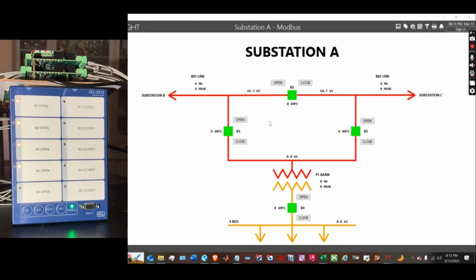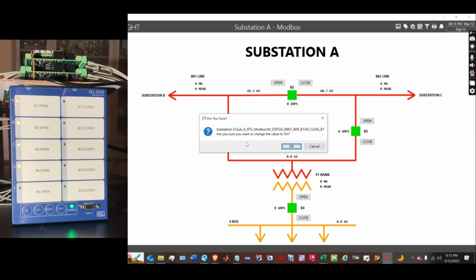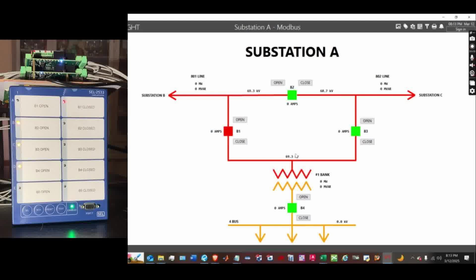are 0. After closing breaker B1 from the SCADA, we get our little pop-up window here asking us to confirm, do we want to close breaker B1? We'll say yes, we do. The breaker turns red to show that it's closed, and we see the voltage on the 69 kV side of the transformer goes up to 69.3 to match the voltage of the 801 line that it's now connected to.